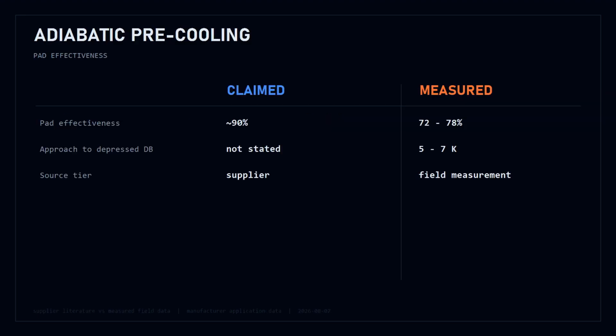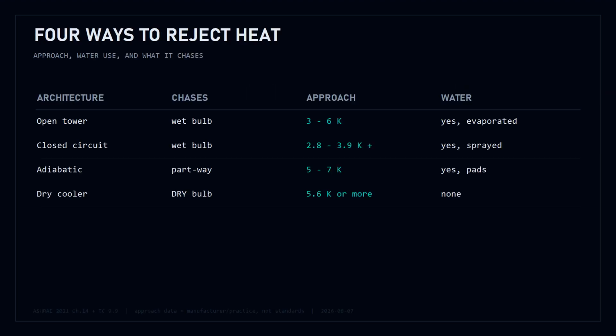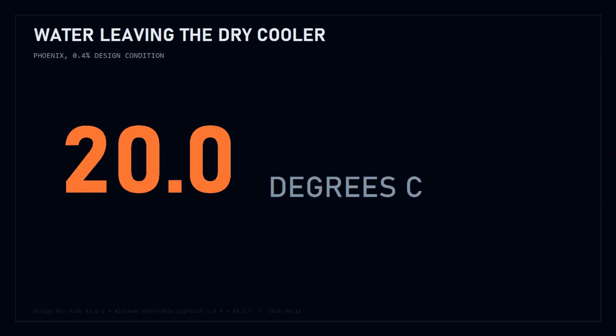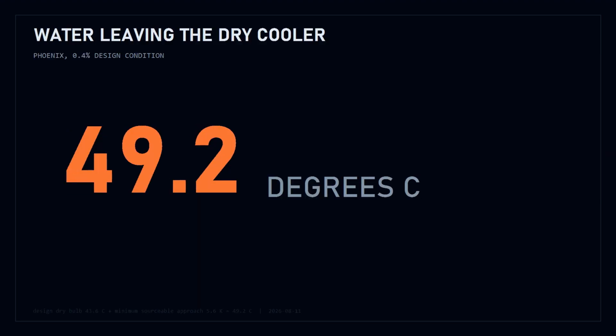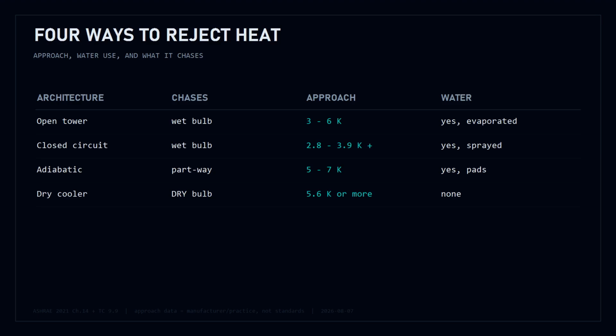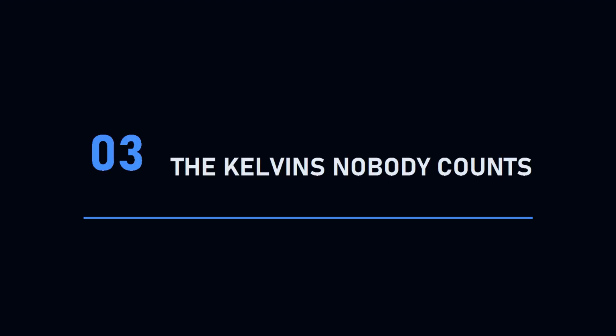An adiabatic cooler, measured pad effectiveness of 72 to 78% against the 90 the suppliers advertise. And a dry cooler does not chase wet bulb at all. It chases dry bulb. And the lowest figure anyone publishes is 5.6. One thing about those 4 numbers, and I want it on the record, not one of them comes from a standard. They are manufacturer application data and industry practice. The standards tell you how to measure an approach. What it costs you in a real machine is somebody's product literature. I will mark them differently on screen for the rest of this video.